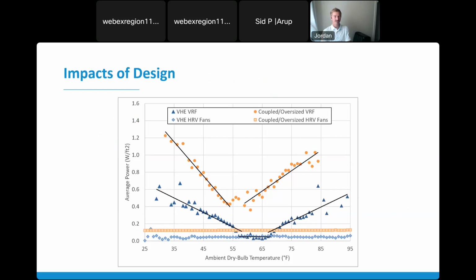Here's another example, and this aligns with the energy code's goals of low fan energy. This is two systems. The blue triangles are the normalized average daily power consumption of the VRF system in a VHE DOAS system. So this is fully decoupled, and followed all the design requirements to a T. And the orange circles are a system that is partially coupled. It's actually the same example from before. This is a system where the VRF system was coupled with the ventilation air, and it was a far oversized system too, which we found to have a big impact on energy usage.